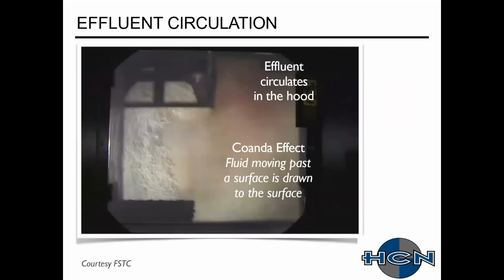The big thing with a listed hood, and a lot of the manufacturers do this, is they have some means to circulate that effluent in the hood and that capture volume. Typically that hot, buoyant air is going to cling to that cooler surface in the back, go up to the filters, and be sucked out. But not all of it's going to be sucked out on the first go through, so it has a tendency to circle back. Some manufacturers use a capture baffle, and I've heard it called a magic triangle. Some companies also use little fans that push the air in. They all accomplish the same thing: we want to recirculate it so it gets sucked back out.